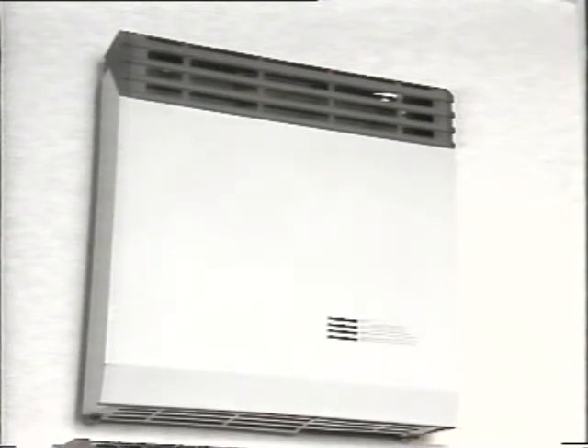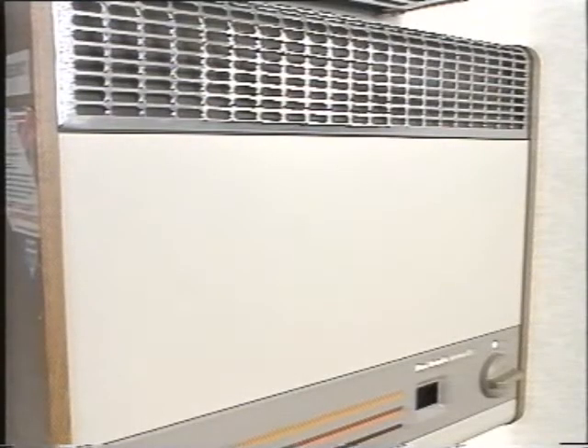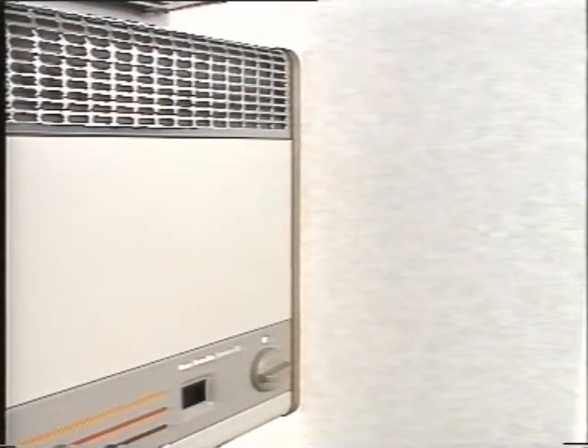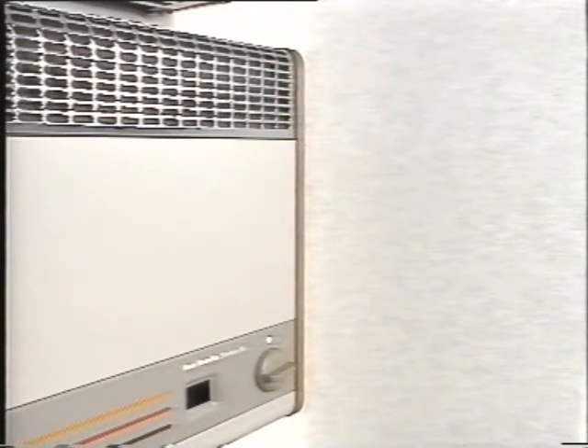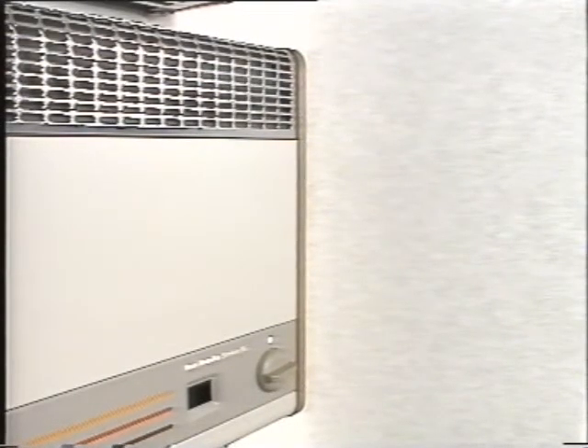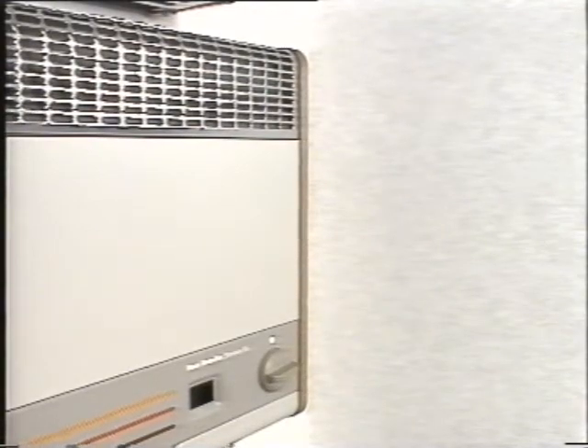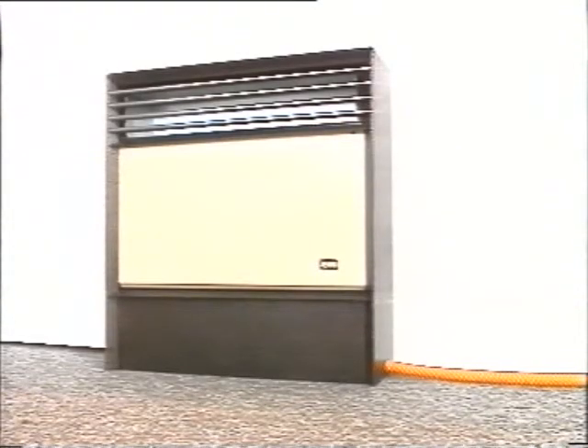If you're installing a convector heater, there's one difference. You've got to make sure that no part of the combustible sidewall is less than 150 millimeters from the warm air outlet. Again, though, check the manufacturer's instructions. They may vary depending on the type of heater. If the appliance is fueled by liquefied petroleum gas, the same rules apply that we quoted in connection with cookers, i.e., it'll need special valves and connections, and it has different installation and ventilation requirements.